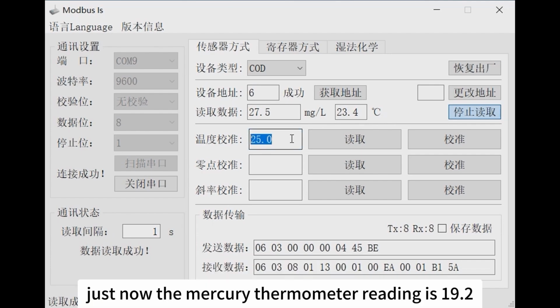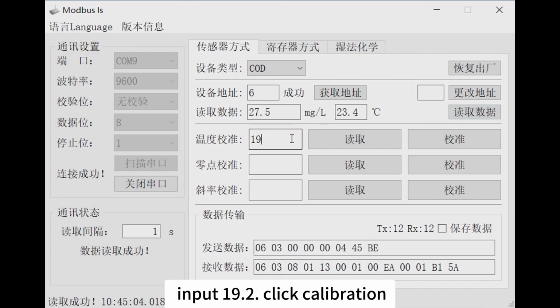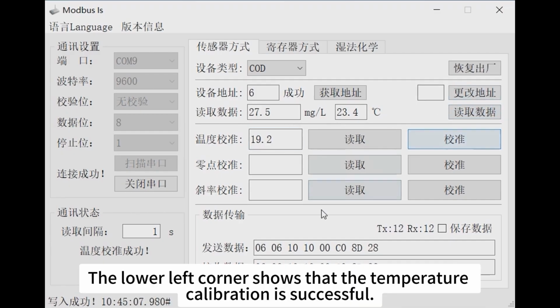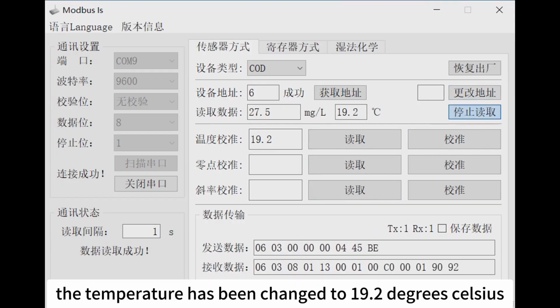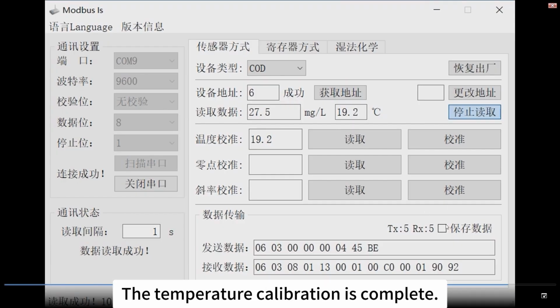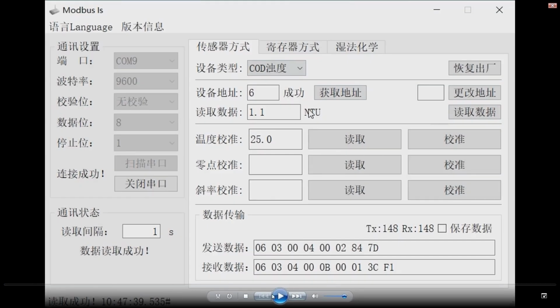Just now the mercury thermometer reading is 19.2, input 19.2. Click Calibration. The lower left corner shows that the temperature calibration is successful. Read the data. The temperature has been changed to 19.2 degrees Celsius. The temperature calibration is complete.